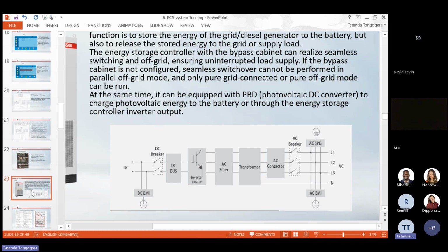So in that event, now you have your current limit exceeded, maybe for one phase or all the phases. So your system will start tripping and then you start fighting with the clients. So it's best that when you're doing your load analysis, you check what the peak currents are. Always take note of the peak currents and which devices are causing those currents. And then you put drives on all motors which are above 10 kilowatt.